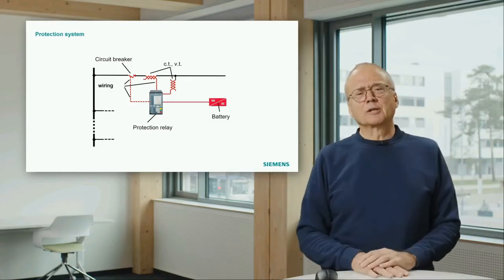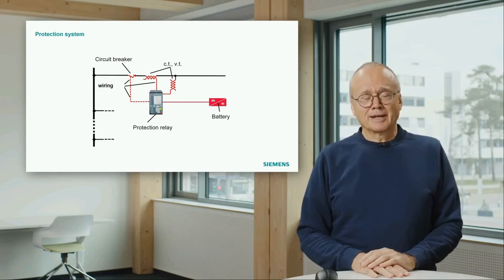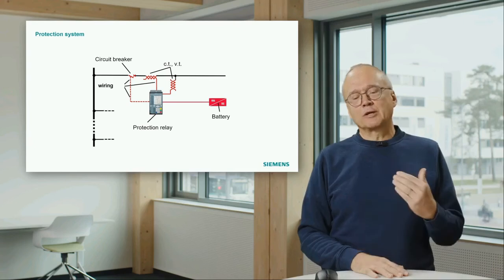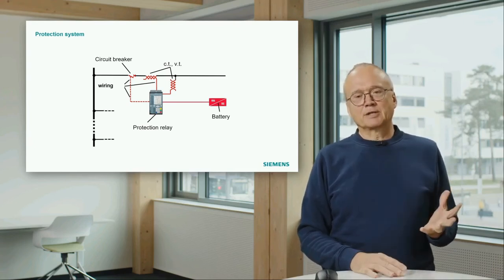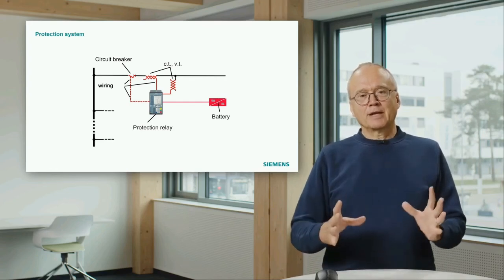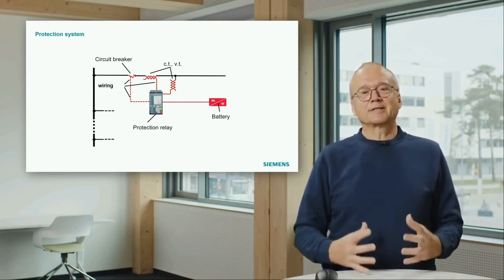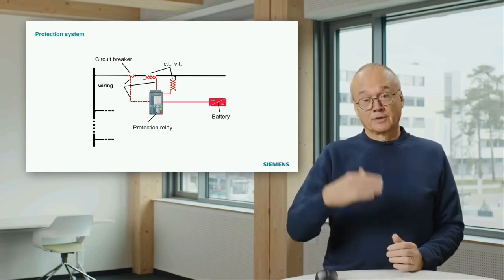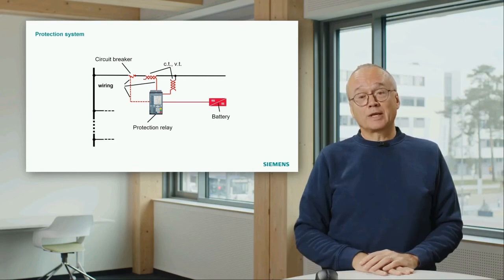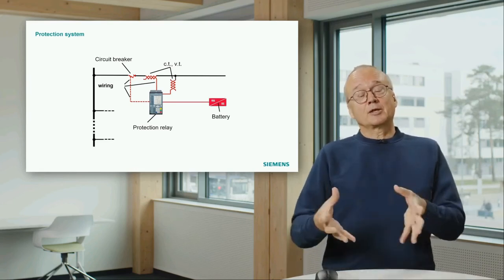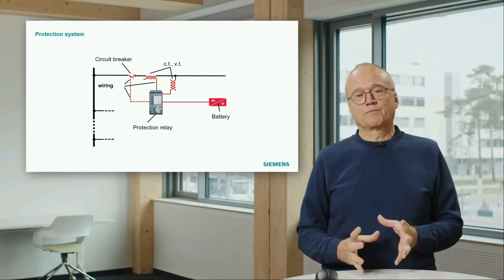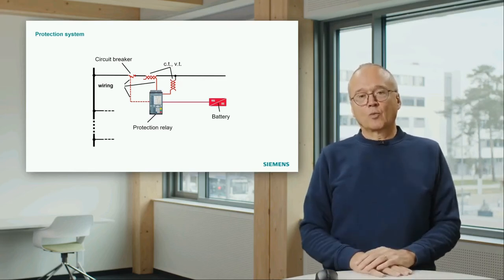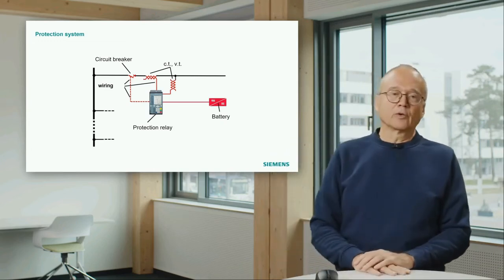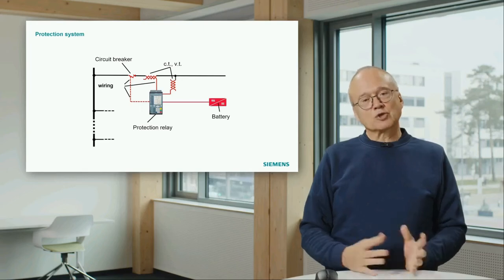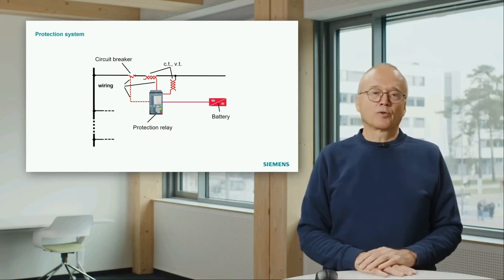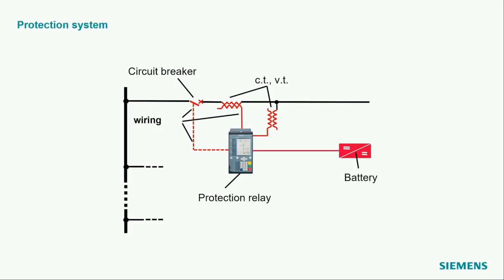Of course, wiring looks a little bit trivial in this sketch. Yes, it's trivial, but if you think about a big open air substation, then you have the circuit breaker, the VTs and CTs outside in the field. You always have to multiply what you see here by 3, because we have the 3 phases. And the protection relays are somewhere in a relay house. Now you can imagine you have a lot of wires, and these wires can be 100 meters long or longer. So sometimes things happen with the wiring, so we sometimes also have to pay attention to that.